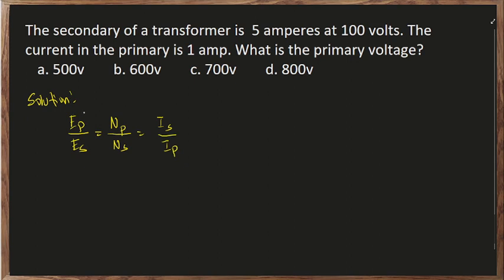So ang gagamitin natin na ratio is yung given kasi natin is voltage and amperes. So ang ratio natin is between the voltages and the currents. So isa-isahin muna natin yung given. The secondary voltage is equal to 100 volts, habang ang kanyang secondary current is 5 amperes. Then our primary voltage, yun yung hinahanap, but we have our primary current which is equal to 1 ampere. So using the ratio, primary voltage over secondary voltage is equal to secondary current over primary current. So hinahanap natin is itong primary voltage, so ilipat na natin to dito.